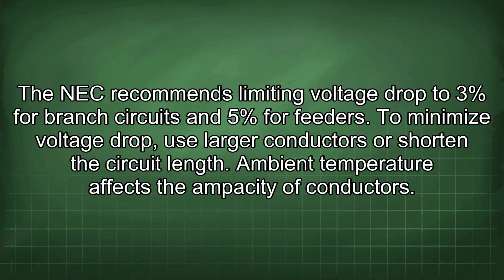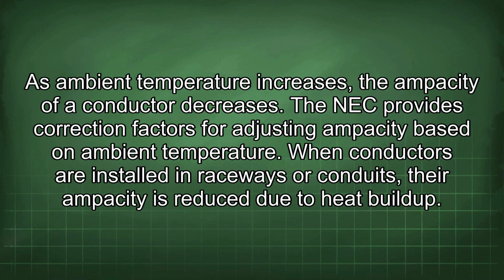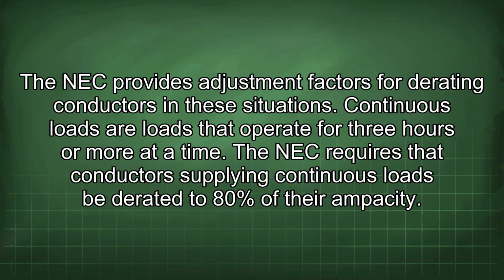Ambient temperature affects the ampacity of conductors. As ambient temperature increases, the ampacity of a conductor decreases. The NEC provides correction factors for adjusting ampacity based on ambient temperature. When conductors are installed in raceways or conduits, their ampacity is reduced due to heat buildup. The NEC provides adjustment factors for derating conductors in these situations.